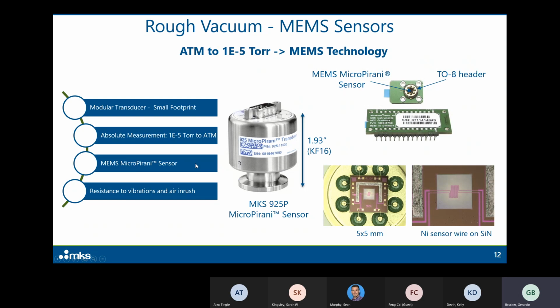And the reason it can do that in such a small package is it benefits from our very own MEMS micropirani sensor, which is quite an advantage over traditional Pirani sensors, which rely on a single wire, because by being a little modular, tiny little chip as it is, it has resistance to vibrations, and it's also very resistant to air inrush. And on the right side here, you can see what the MEMS sensor that is inside this device looks like. That's a TO-8 header, which is smaller than a penny, and in the center of it is the Pirani sensor, which right here on the bottom you can see what it looks like. It's a 5mm by 5mm chip, and the actual active sensing element, the heated wire or heated sensor, is right here in the center, which is blown up here, and it's just a nickel sensor wire on a silicon nitride membrane. Such a small sensor is what makes it possible to make such small controllers.